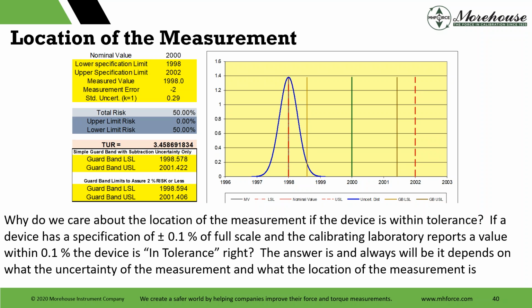So why do we care about the location of the measurement if a device is within tolerance? If it has a specification of 0.1% of full scale and the calibrating laboratory reports a value within 0.1, is it in tolerance, right? No, I just told everybody. The answer is, and it always will be, it depends on what the uncertainty of the measurement is and what the location of the measurement is.